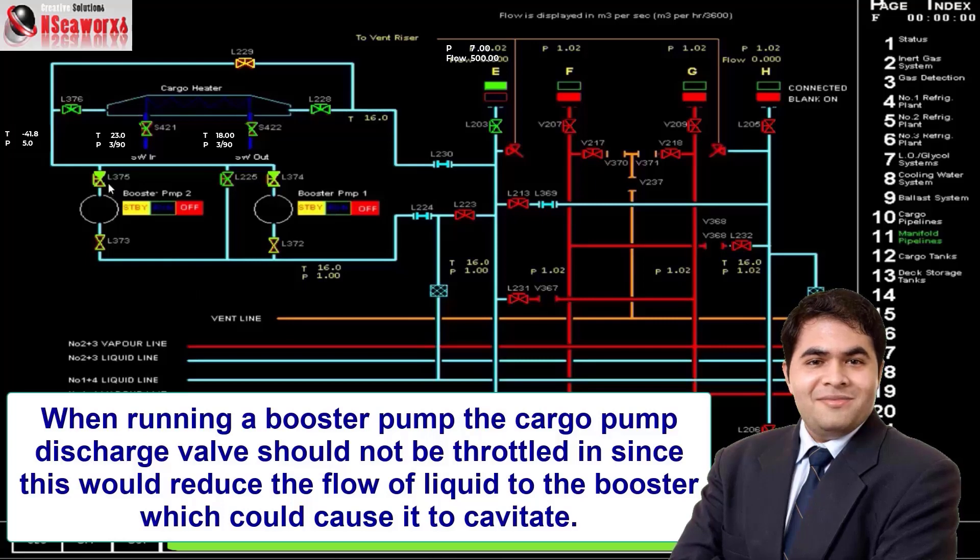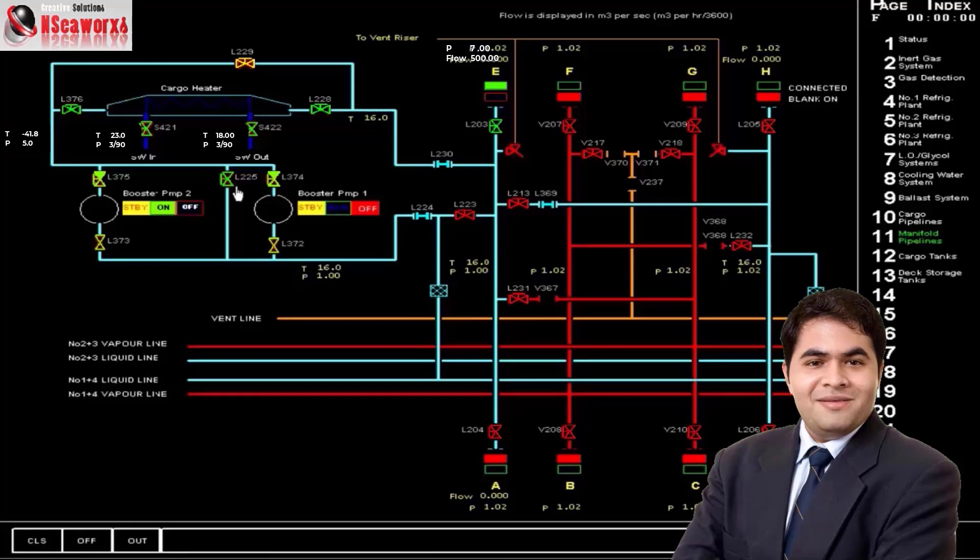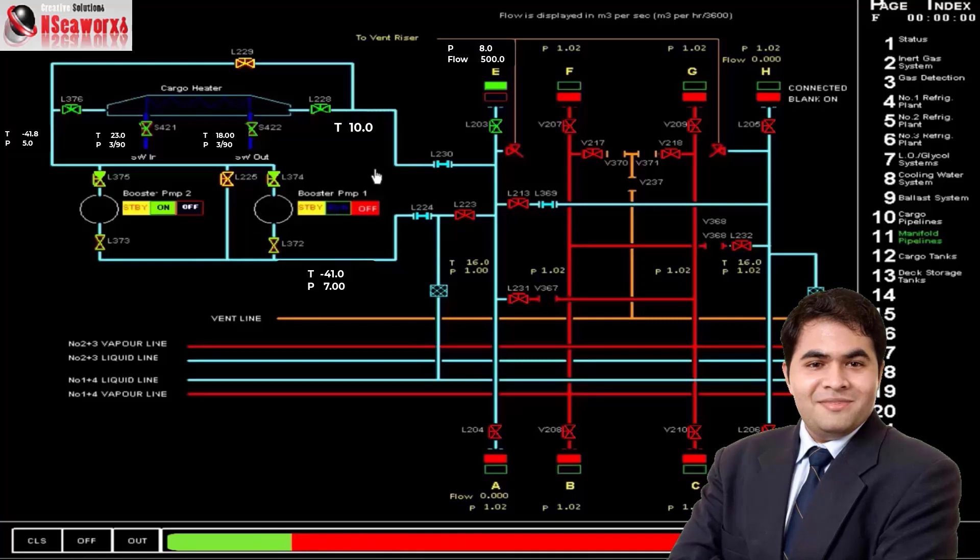The booster pump will control the discharge pressure, not the cargo tanks pump. Now that you are ready, then you can start. Let's say we start one pump. And we just start closing the circulation valve until you meet the required discharge pressure. In this scenario, you are still using the cargo heater. So it should be okay. But you have to adjust as well because you are now using a cargo booster pump and the flow will become faster.